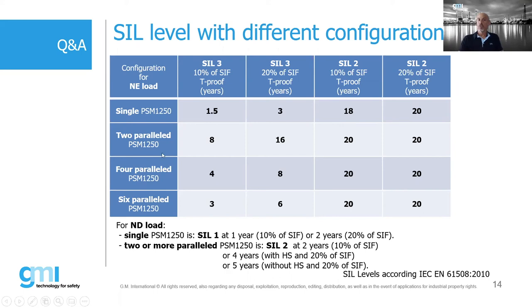If I use two parallel power supplies, you see that those numbers increase by a lot. Four parallel, six parallel, also a little bit more. But I want to draw your attention to the fact that if I have a SIL3 power supply and I want to use it for a SIL2 application, I can use the same power supply for a very long time without any testing. The application here is also for a normally energized load, where we change the parameters a little bit. So I think it's now clearer for you, also the question about redundant and non-redundant, proof testing and so on.